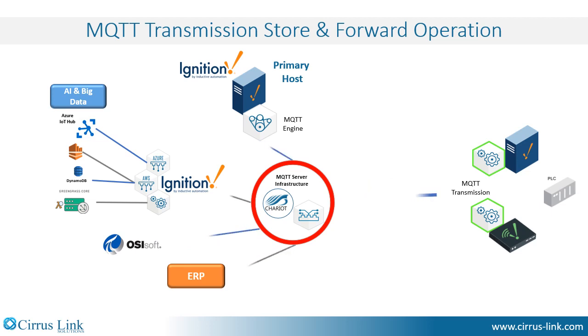If any part of the system required to deliver data becomes unavailable — such as the communications, the MQTT server infrastructure, or the primary host itself — data is immediately stored locally by transmission. The primary host ID is a notion supported by MQTT Sparkplug, where a critical application such as the SCADA HMI has its status notified to MQTT clients that are connected, in case it fails, causing the clients to initialize local data storage.